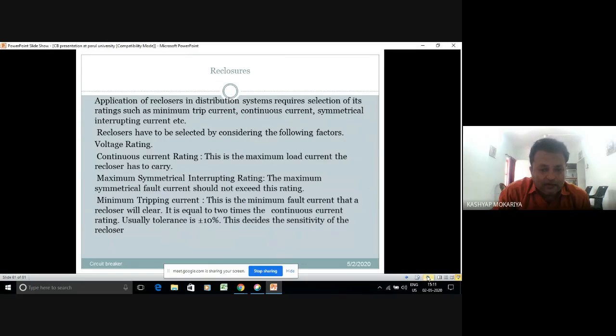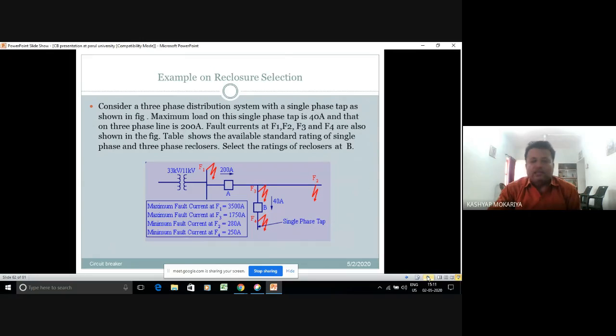I have taken one design application, that's why I'm moving, because I'm parallelly looking at the watch also. So consider a 3-phase distribution system with single phase tap as shown in the figure. Maximum load on this single phase tap is 40 ampere, and on the 3-phase line, suppose it has 200 ampere, so you can see the fault currents at F1, F2, F3, F4 are also shown. They are asking to select the rating of recloser at B.